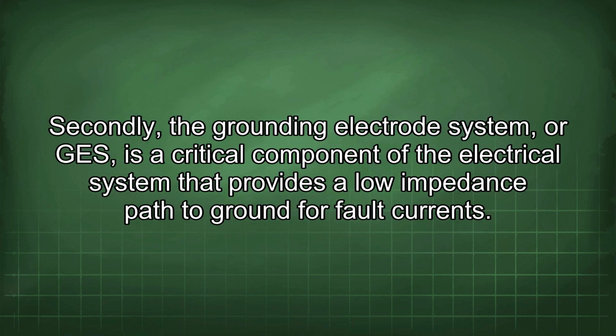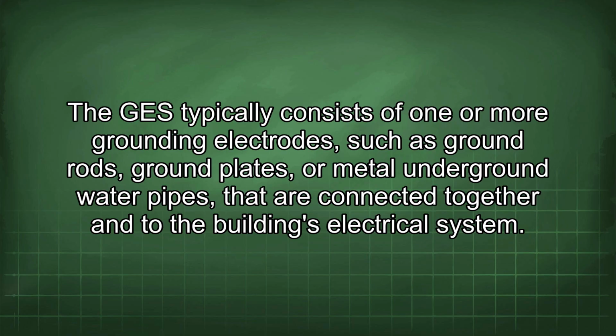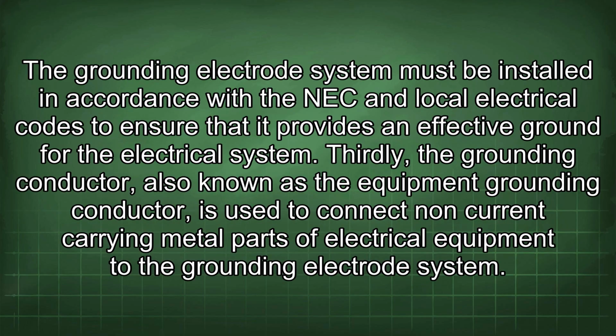compliance. Secondly, the grounding electrode system, or GES, is a critical component of the electrical system that provides a low impedance path to ground for fault currents. The GES typically consists of one or more grounding electrodes such as ground rods, ground plates, or metal underground water pipes that are connected together and to the building's electrical system. The grounding electrode system must be installed in accordance with the NEC and local electrical codes to ensure that it provides an effective ground for the electrical system.